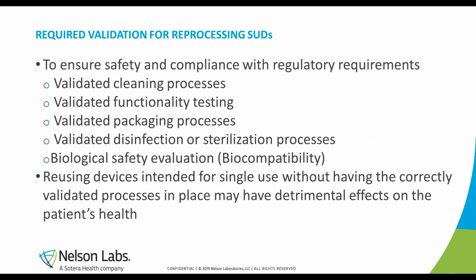Reusing devices intended for single use without having the correct validated process in place may have a detrimental effect on patients' health. Regulatory requirements for third-party reprocessing mandate the development and validation of processes to refurbish the device to substantially equivalent performance as compared to the original device. Because the device was designed for single use, reprocessing instructions have not been developed and therefore require post-market development by the third-party entity.